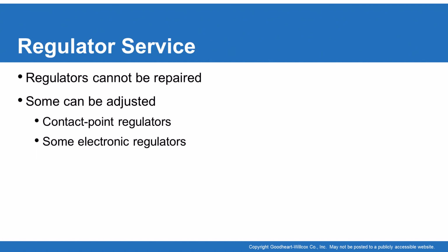Then as far as regulator service, regulators can't be repaired. Most of the circuitry inside them just can't be serviced. Some can be adjusted: the contact point regulator styles have an adjustment in there, and that's only on some regulators that are very old. But for the most part today, the voltage regulator itself is a replaceable unit. And this is actually a very good cost savings measure for most alternators, since this seems to be one of the higher failure points on a vehicle.